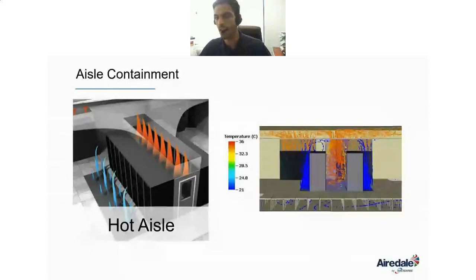Now cold aisle containment or hot aisle enclosures completely segregate the air, preventing mixing. Air into the servers is between 22 to 24 degrees C, while return air to the CRAC unit is 30 to 35 degrees C. This creates a big delta T, and at high return air temperatures the CRAC units are very efficient, also enabling free cooling.